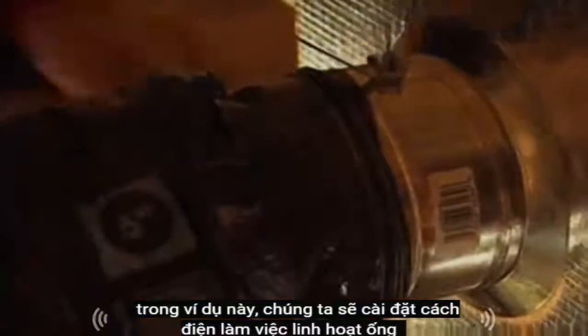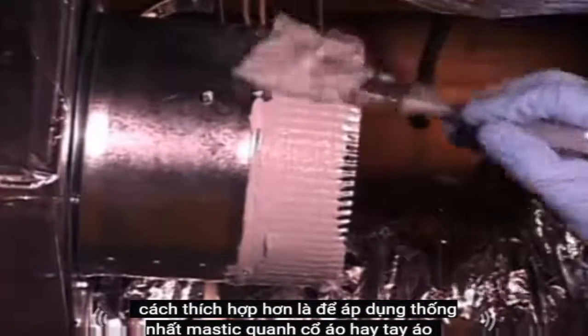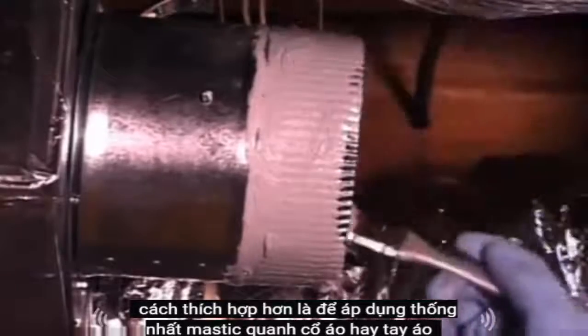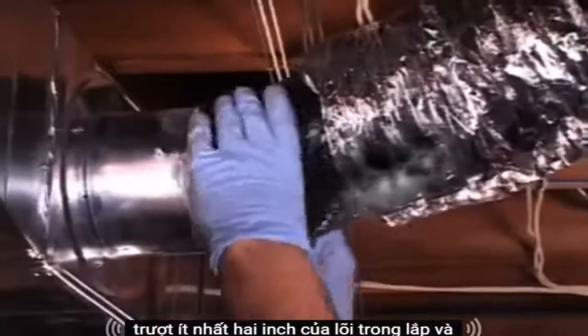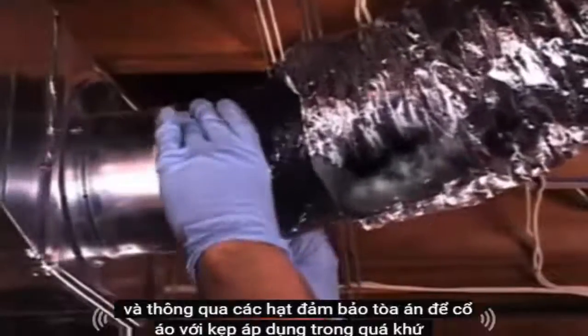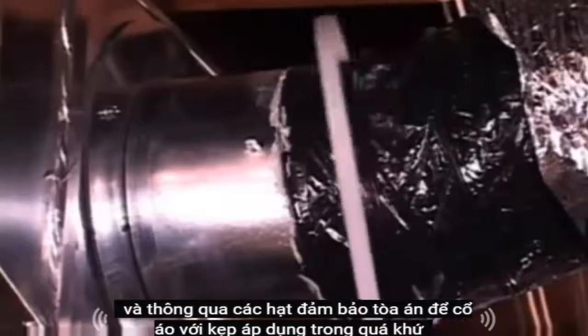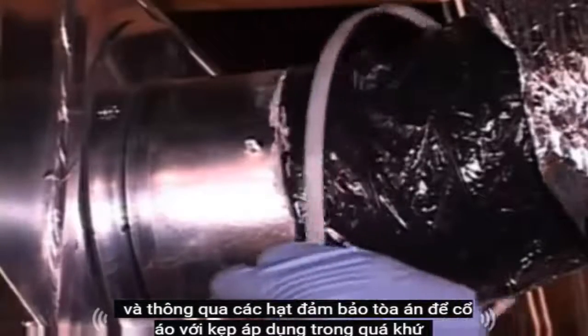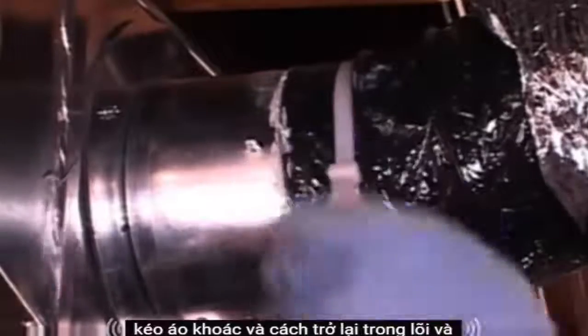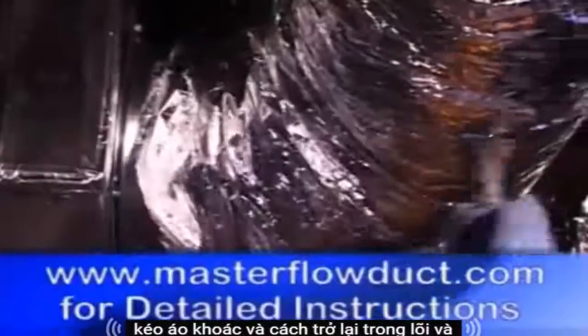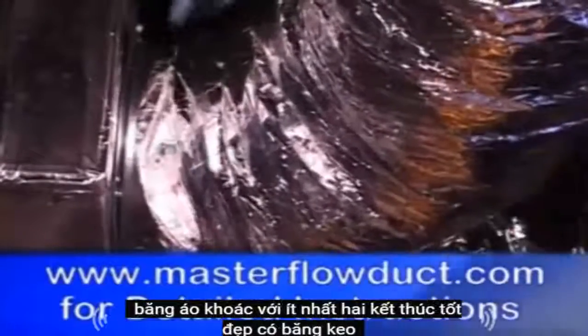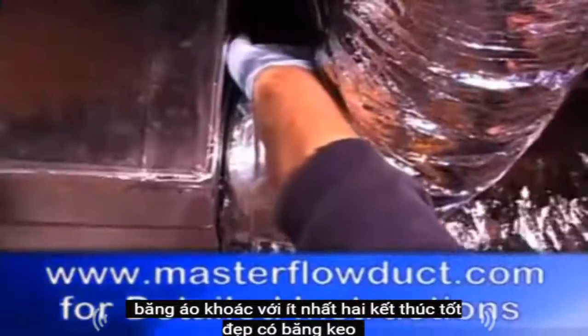In this example, we will install insulated flexible ductwork. When connecting flexible ductwork to a starting collar or takeoff, the preferable way is to apply mastic uniformly around the collar or sleeve. Slide at least 2 inches of core over the fitting end and past the bead. Secure the core to the collar with a clamp applied past the bead. Pull jacket and insulation back over the core end. Tape jacket with at least 2 wraps of duct tape.